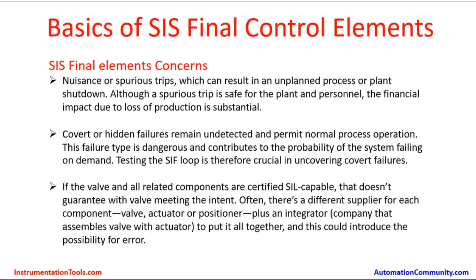Covert or hidden failures remain undetected and permit normal process conditions to continue. This failure type is dangerous and contributes to the probability of the system failing on demand. Proof testing of the SIS loop is therefore crucial in uncovering covert failures. Even if a valve and all related components are SIL-certified, that does not guarantee the valve will meet the design intent. During engineering, the valve should be selected with SIL capability, but having SIL capability does not guarantee it will work as intended.